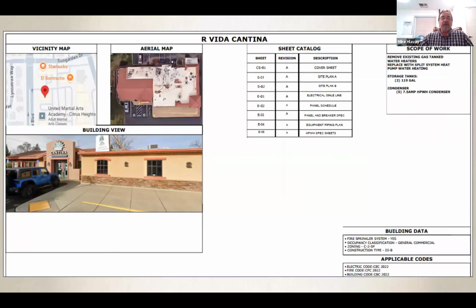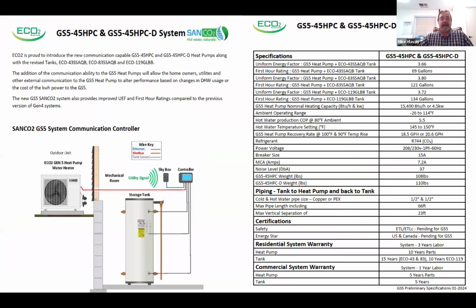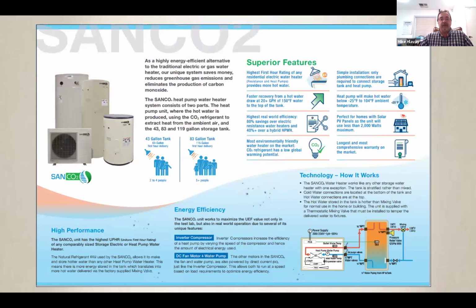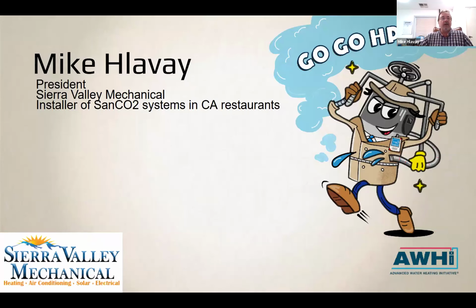That's really all I have to present. As you've probably figured out, we've only installed one heat pump water heater system in a commercial kitchen ourselves. We've installed thousands of heat pump water heaters, including commercial systems, but it's relatively new to our area. While we only have one installation under our belt, we're piling up installations and working through them. So that's my experience installing these systems.